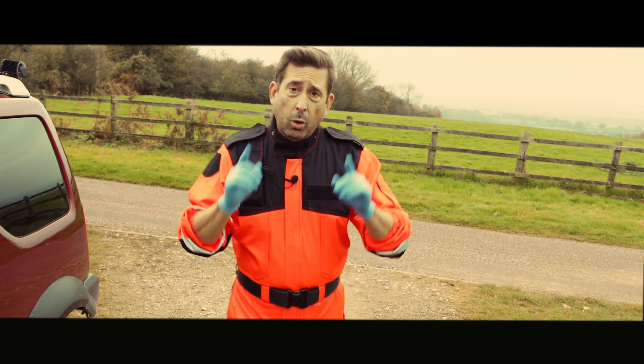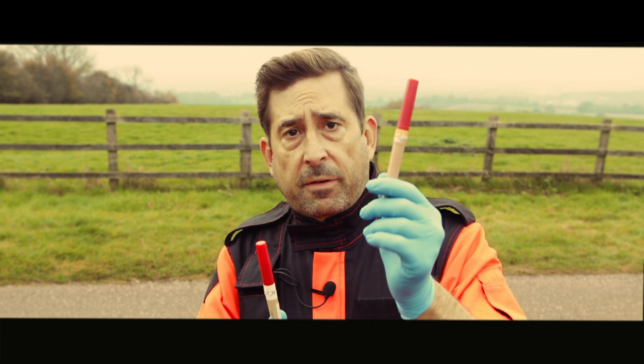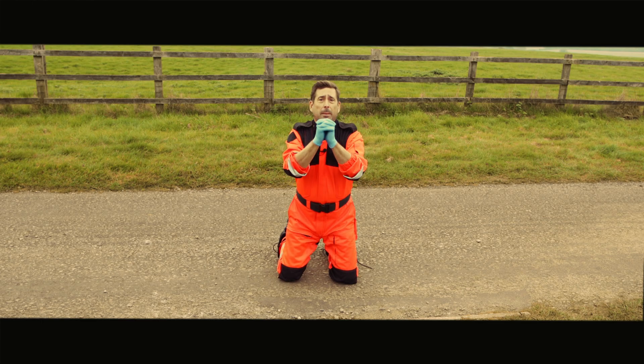Now, a warning on what not to buy. This is a different needle from Titec and a counterfeit I found online. The counterfeit is thinner and its plastic catheter is softer, therefore potentially prone to kinking. Please buy original medical devices.